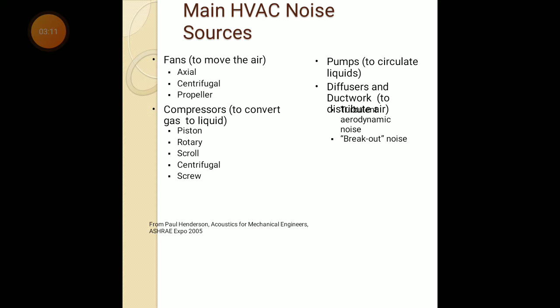Third type of source is pump. On a large scale basis, for cooling purpose, we require a pump which circulates liquid, generally water, continuously to the cooling tower. So pump is one of the sources which generates noise. Next, diffuser and duct work. Generally, if the velocity of conditioned air is very high, it generates noise, and if it is fitted with a diffuser at the end, then again breakout noise can also be produced. So these are the different sources of noise.